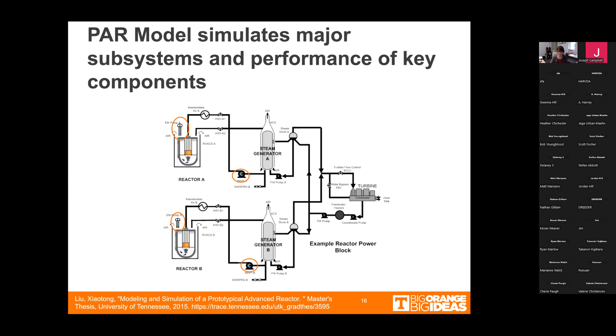As we degraded the pumps so they couldn't produce as much flow as demanded, it impacted the maximum power output from the system. So we're really looking not at safety here, but at economic viability - are we able to meet demand? As the primary pump's flow rate capability decreases, there's a linear decrease in maximum power output, and the intermediate pump shows a similar but smaller impact.